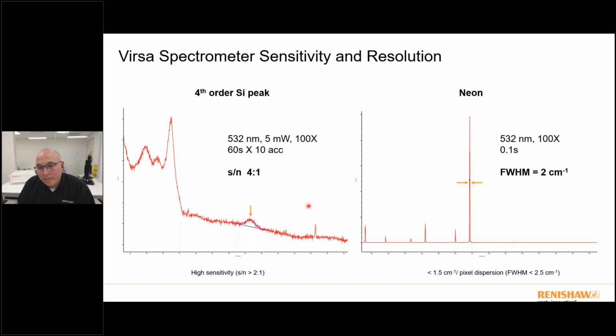In terms of performance, I have a couple slides here which really highlight the capability of this instrument, because that was our goal. We wanted to have portability, a benchtop type system, but also have the ability to do things that the inVia Raman system can do. So in terms of sensitivity, we measure the 4th order silicon peak, which is a pretty common test. In this case, I'm actually measuring close to 4:1 signal to noise based off of the peak to peak height in the noise area relative to the 4th order peak. Our spec is generally a signal to noise better than 2:1.